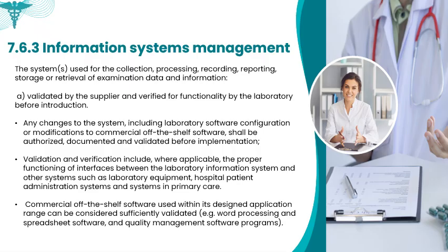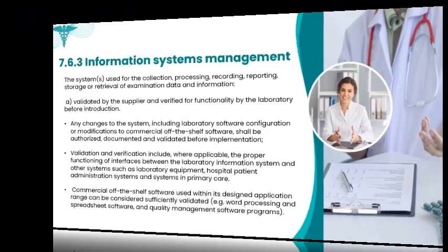Note 1. Validation and verification shall include, where applicable, the proper functioning of interfaces between the Laboratory Information System, LIS, and other relevant systems such as laboratory equipment, hospital patient administration systems, and systems in primary care. Note 2. Commercial off-the-shelf software, when used within its designed application range, may be considered sufficiently validated, for example, word processing, spreadsheet, or quality management software.